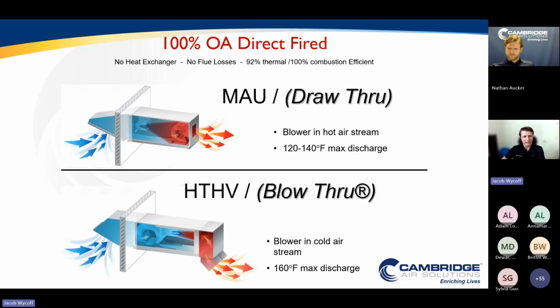So, similar to a makeup air unit, HTHV units are going to be 100% outside air, direct fired pieces of equipment. You're going to get that great direct fired efficiency of 92% thermal efficiency because the combustion is happening directly in the airstream and you don't have any flue losses. Makeup air units, as you can see, have the blower downstream of the burner, with that blower in the hot air stream. And this is fine when your main concern is providing large amounts of makeup air and your discharge temperature doesn't need to be as high. But when you have that blower in the hot air stream, you're going to limit your discharge temperature to anywhere around 120 to 140 degrees.